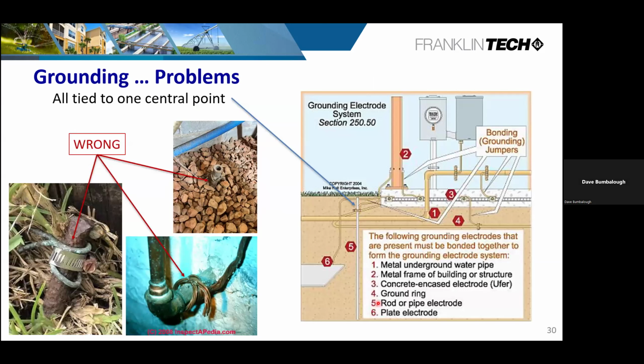Things to look for out in the field: improper grounding, using a hose clamp, not even securing the grounding media, using the wrong materials. This particular picture was actually inside of a pump house, where I can assure you it's not moist in there. As you can see, everything's dry here. So you want to make sure that you're using the right materials, connecting correctly, and bonding your equipment as shown in this section, Article 250.50, about bonding and making sure everything is tied back to one general location. Very crucial. If this is not done, you open up the potential for leakage voltage and some potential issues with failing equipment.